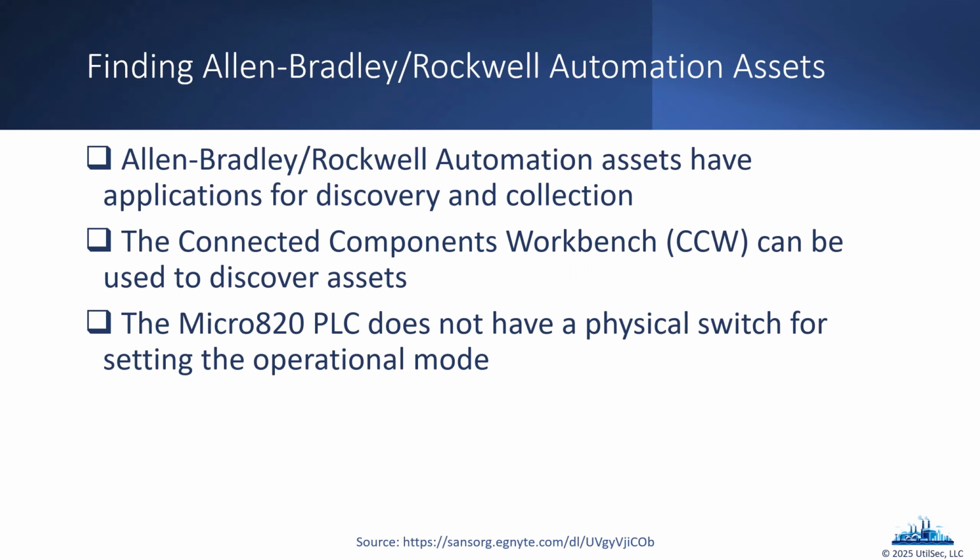Now, for my master's project, I had this idea where I wanted to set up a simple web page that would allow someone in an OT environment, and it would connect to their different PLCs and determine whether the PLCs were in run mode or not. And then if you had a PLC that ever came out of run mode, which means it's going to be in a less secure mode, you would get an alert that you would investigate. Because we want all of our PLCs in run mode. Because yes, it does mean it's in a more secure state.